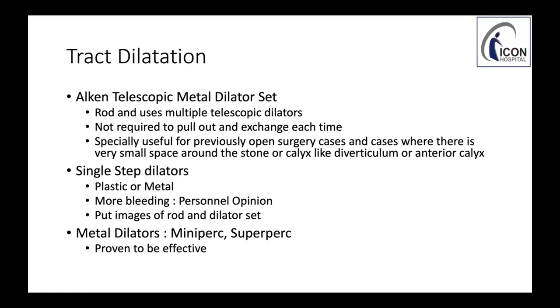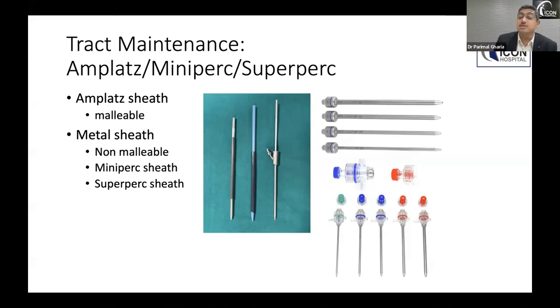Then tract maintenance. By tract maintenance we mean that once we have dilated the tract, we have to maintain the tract till the procedure is over. In those cases, we routinely use Amplatz sheaths. Amplatz sheaths are plastic dilators and are sometimes malleable. So whenever you use a plastic Amplatz sheath, if the stone is not fitting the size, the M+ sheath can be moldable and in that case the stone can be removed. Another are the metal sheaths, which are non-malleable. These can be either mini perc sheaths or super perc sheaths, which are commonly used.